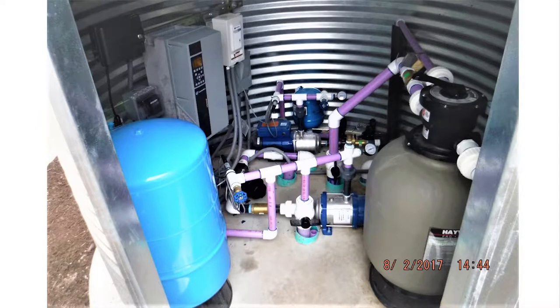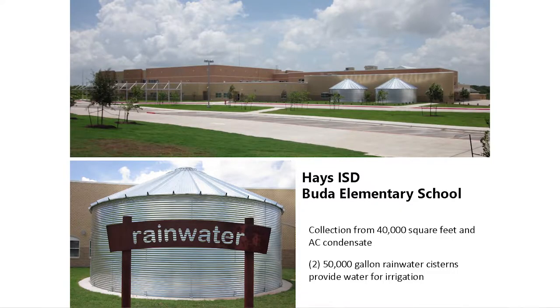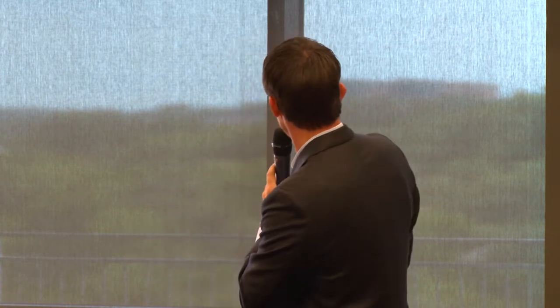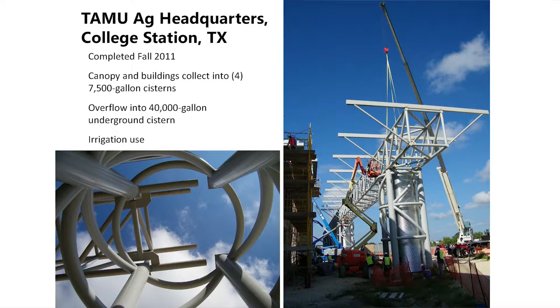This is a neat project because of how they showcased the rainwater system out front — (2) 50,000-gallon tanks collecting both rainwater and condensate from about 40,000 square feet. Here are some pictures of the pump setup, which is just for irrigation. Again, this is where we come back to matching quality and design to the needs: for an irrigation system, do you really need a sophisticated UV disinfection system? This one also has a water meter so the school can track the amount of water they're saving.